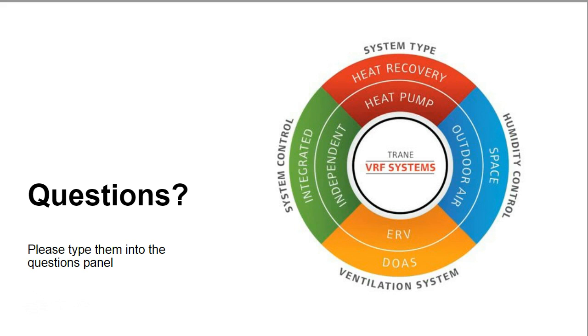The next one is, what is the best way to estimate the amount of refrigerant charge needed for a VRF system, including the charge for pipes inside? So this question, I always come back to the VRF manufacturer's system selection software. There are old methods of being able to just determine additional refrigerant using pipe sizes and lengths. Although with the complex systems that we are seeing today, it's a much more accurate method by entering in those lengths and pipe sizes.